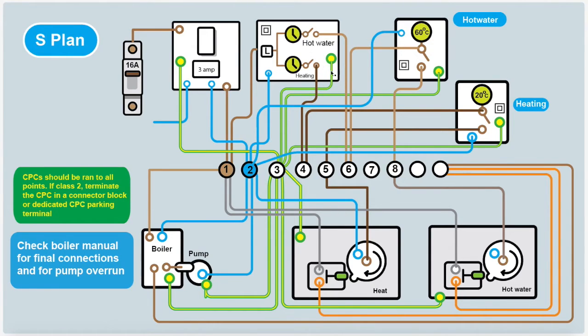So in class two, for example, you would put the CPC in a parking spot. There's sometimes a little CPC parking spot, a little earth nut to put it into, or if not, just put a little connector block so it doesn't move about and can't touch anything. So you always want a CPC to every point.